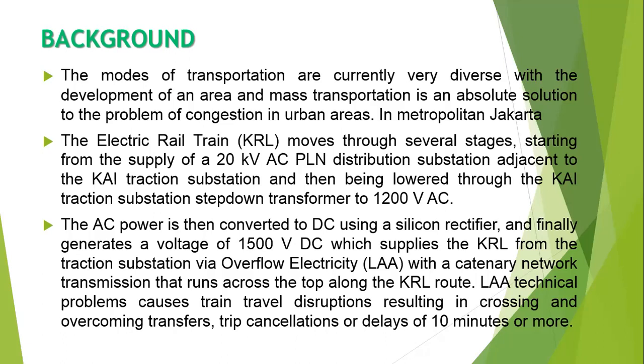The electric rail train moved through several stages, starting from the supply of a 20 kilovolt AC PLN distribution substation adjacent to the KAI traction substation, and then being lowered through the KAI traction substation step-down transformer to 1200 volt AC. The AC power is then converted to DC using a silicon rectifier and finally generates a voltage of 1500 VDC, which supplies the KRL from the traction substation via overhead electricity or LAA with a catenary network transmission that runs across the top along the KRL route.